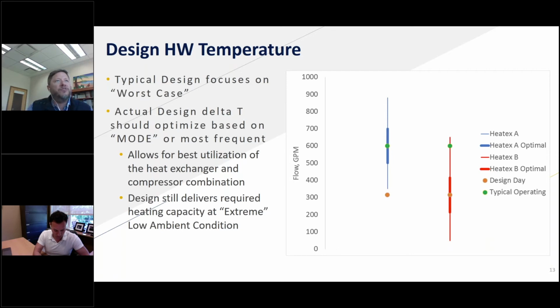But what we would not do necessarily is set our flow rate and our delta T at that point. What we would do is set it at a higher ambient, and then as we reduce that ambient temperature, we can deliver the capacity and the water temperature at a lower flow rate, which means we might have a higher flow rate, which would mean we might have a slightly smaller delta T, but we're still delivering the water temperature and the BTUs that you need for the space. And the end result is you have a far more efficient and effective system for the 90-something% of the time that we're running and heating versus the 1 to 5% for that extreme worst case scenario.